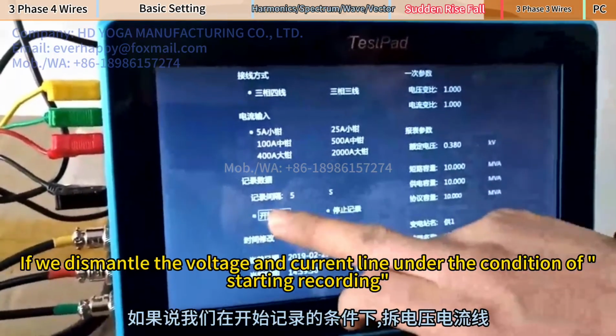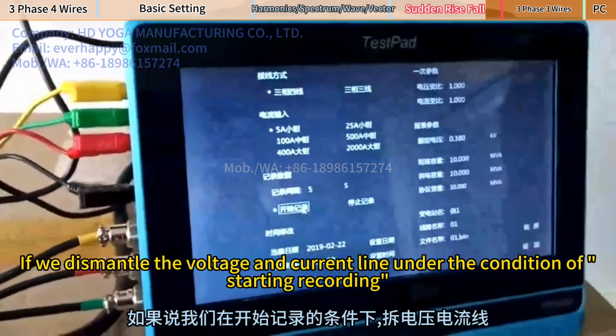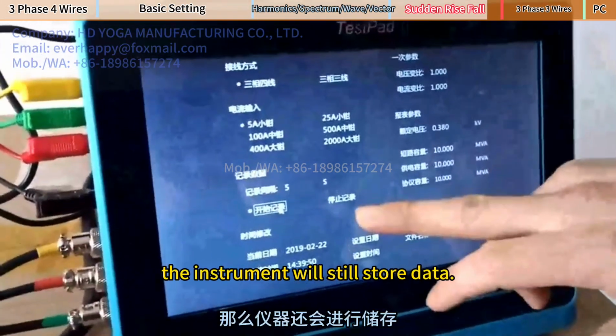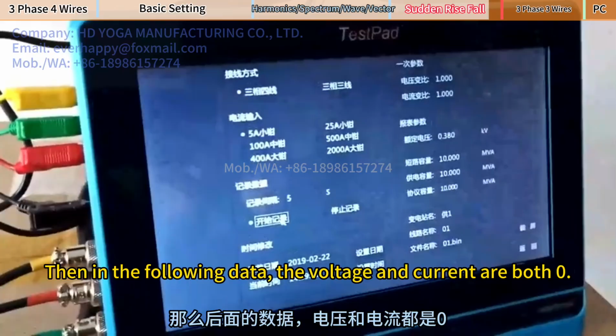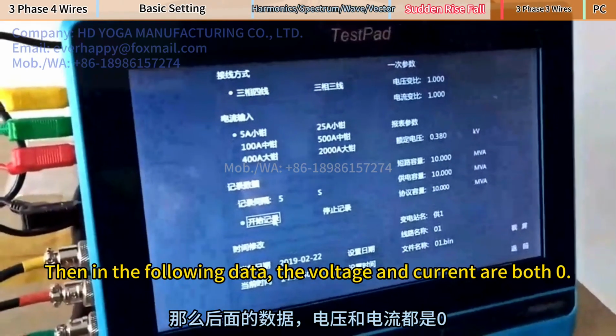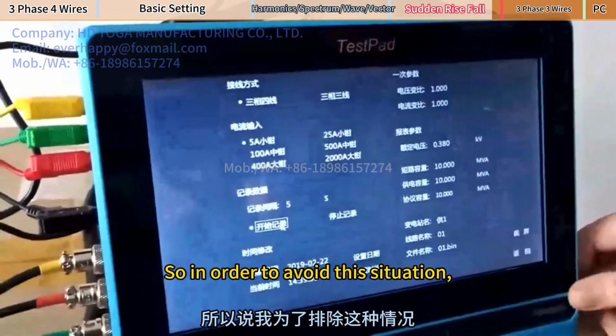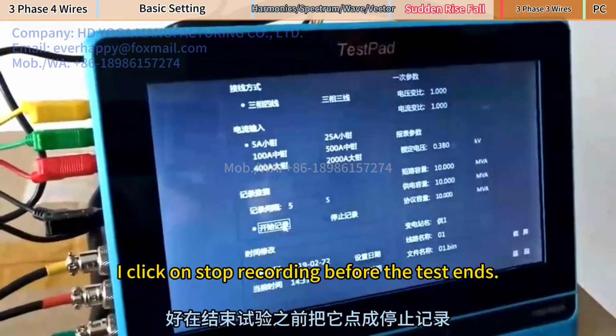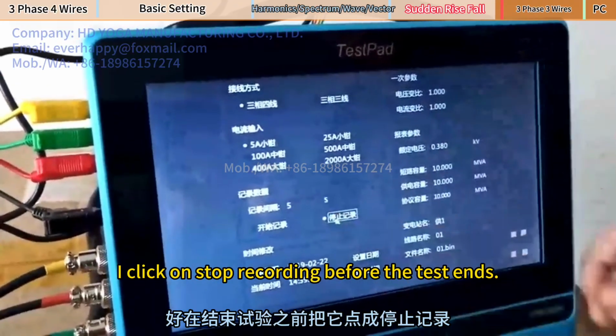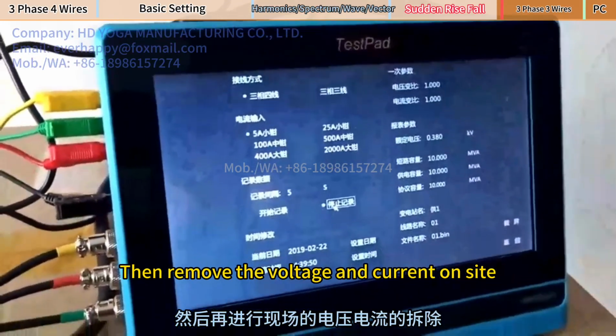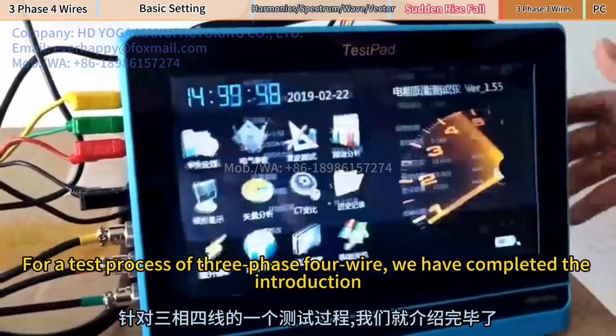If we dismantle the voltage and current line under the condition of starting recording and end the test, the instrument will still store data. Then in the following data, the voltage and current are both 0. Then these are invalid data. So in order to avoid this situation, I click on stop recording before the test ends. Then remove the voltage and current on site. For a test process of 3-phase 4 wire, we have completed the introduction.